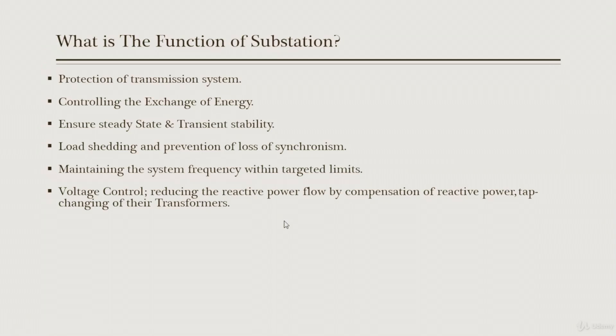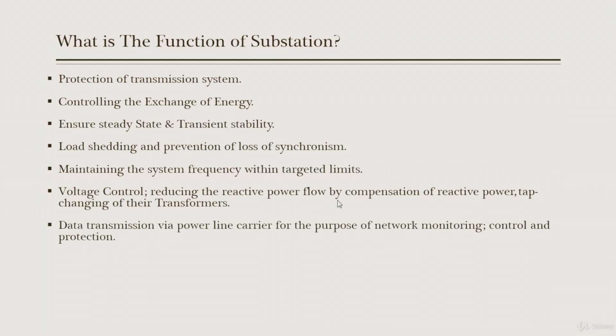To compensate, we use capacitor banks which supply reactive power Q, causing our voltage to increase again. In transformers, we have tap changers which change the number of turns, and changing the number of turns causes a change in voltage — this will be explained further when we discuss transformers. The substation can also be used for data transmission via power line carrier for the purpose of network monitoring, control, and protection.